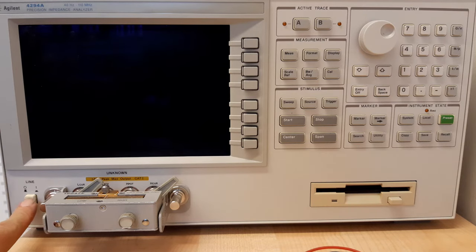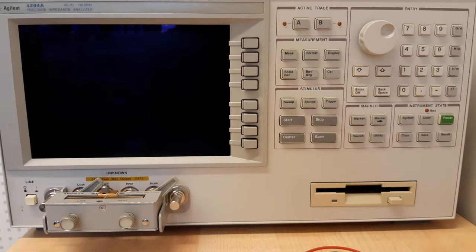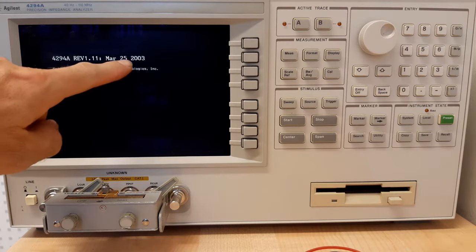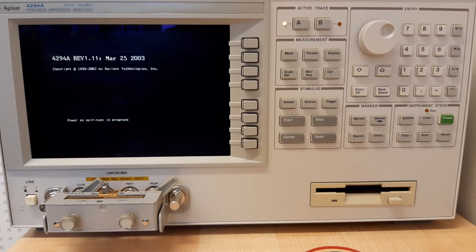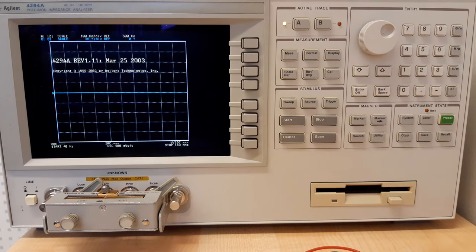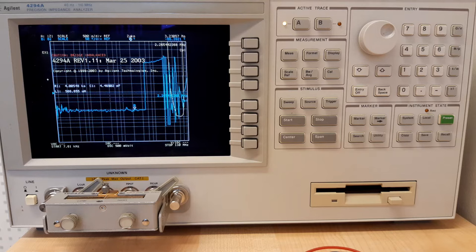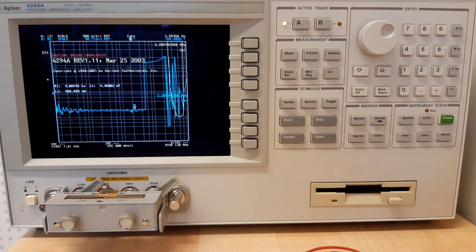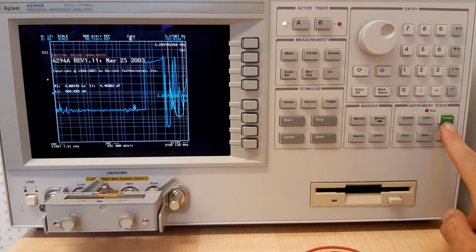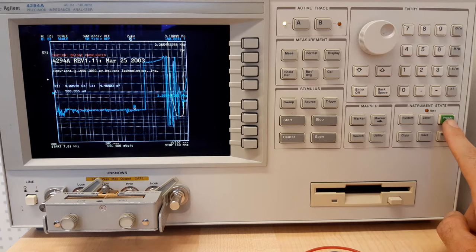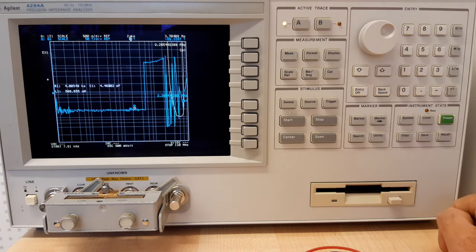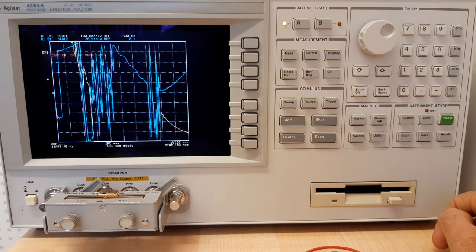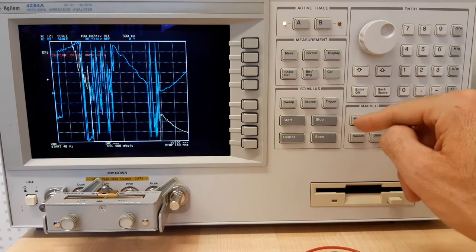Let's take a closer look at the instrument. I'll switch it on again and you can see it booting up, the fan starting to blow, making some noise. This instrument is from 2003, quite old, but it still performs very well. It runs very basic firmware, not Windows. Now that it's started, the first thing you want to do is press the preset button — the green one — to put the instrument in a default state, since you don't know what strange settings a previous user may have set.